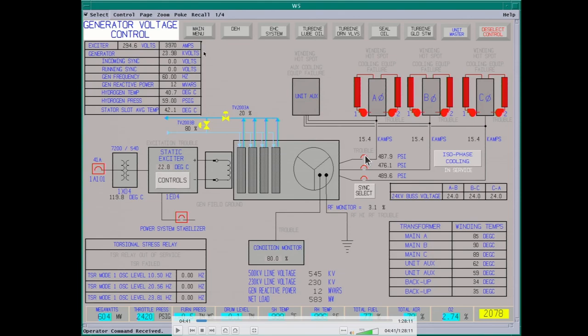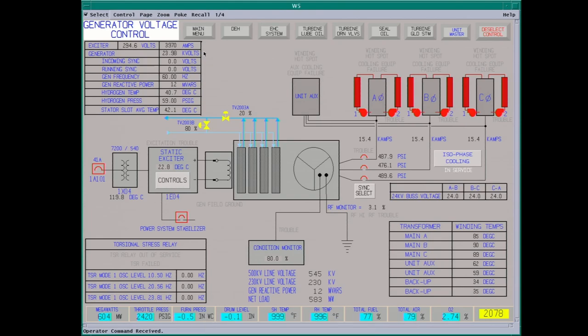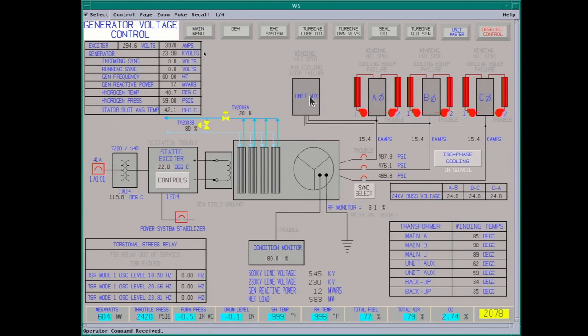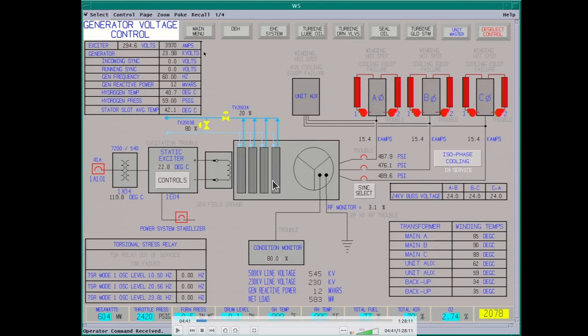The big thing on this screen is the generator breakers — each phase has its own breaker. The transformers step the voltage up to 500,000 volts, and each phase has a transformer. You have a unit transformer that takes the 24,000 volts off the generator and drops it to 7,200 volts for in-plant use. There's a static exciter control breaker, a condition monitor that looks for particulate in the hydrogen gas stream indicating insulation breakdown, and a radio frequency monitor that looks for shorts or arcing. There's also a power system stabilizer that tries to take the swing out of the power systems.